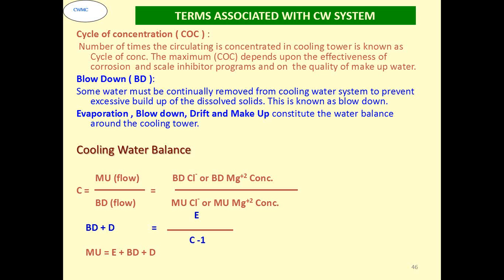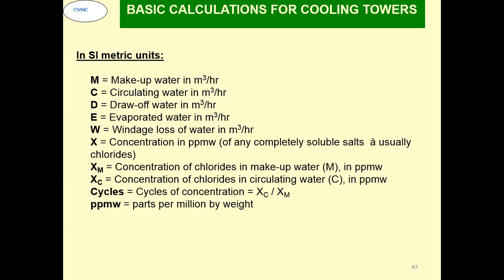If you look at the evaporation, blowdown, drift and makeup, the general relationship is C equals the flow rate of makeup divided by the flow rate of blowdown, or equal to the blowdown chloride level divided by the chloride concentration in makeup, or the blowdown magnesium concentration divided by the magnesium concentration in the makeup. That will give us the cycles of concentration. Blowdown plus drift is equal to E divided by (C minus 1), where BD is blowdown, D is the drift, E is the evaporation and C is the cycles of concentration. Total makeup is evaporation plus blowdown plus drift. So these are the metric units for that.